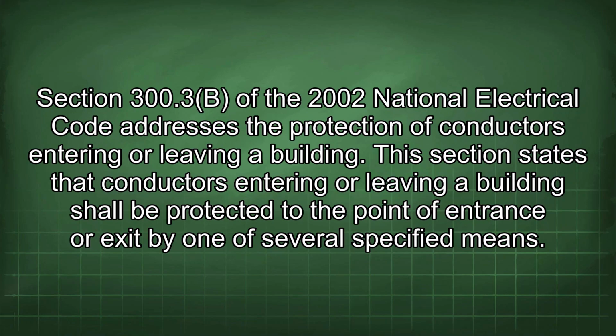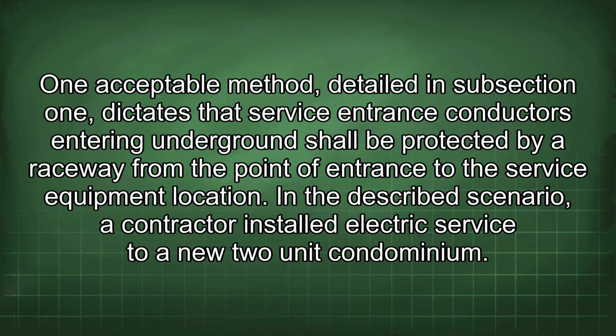Section 300.3b of the 2002 National Electrical Code addresses the protection of conductors entering or leaving a building. This section states that conductors entering or leaving a building shall be protected to the point of entrance or exit by one of several specified means. One acceptable method, detailed in subsection 1, dictates that service entrance conductors entering underground shall be protected by a raceway from the point of entrance to the service equipment location.